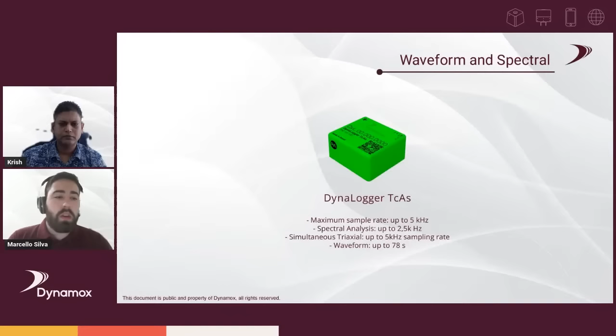In terms of the HF Plus, the maximum sample rate will go to 26 kilohertz, which will guarantee us a spectral analysis up to 13K. And of course, the waveform up to 164 seconds, so almost 3 minutes of collection. This is very important and relevant for low speed applications. If you have any, such as reclaimers or mills, this sensor will be ideal. As you can see, the TcAg is not here. The TcAg is called the global one, and that sensor specifically does not perform any spectral measurements.